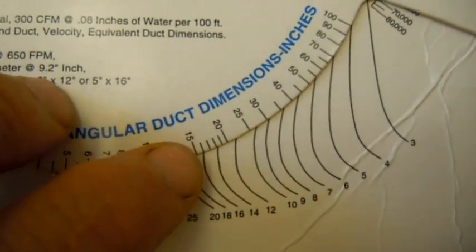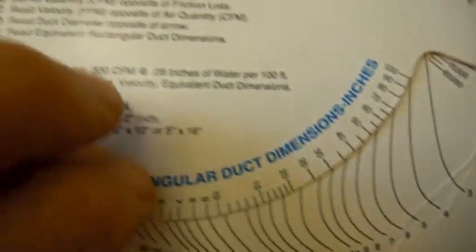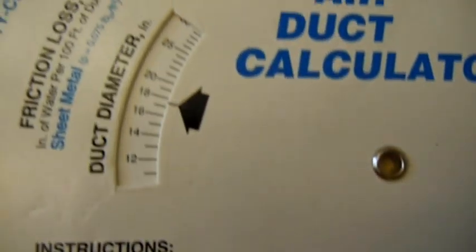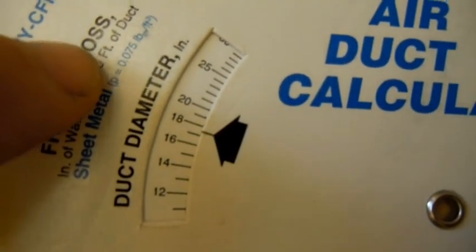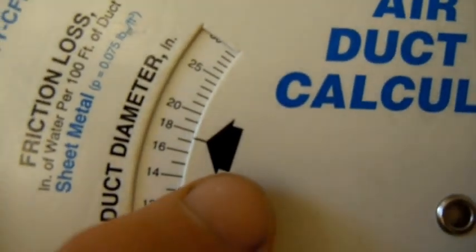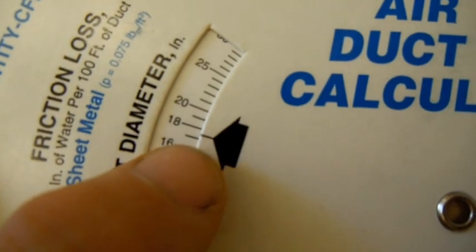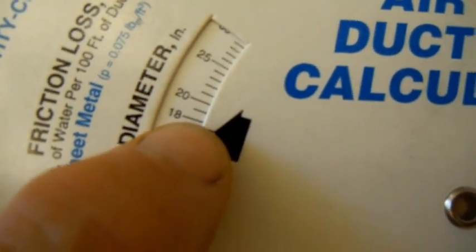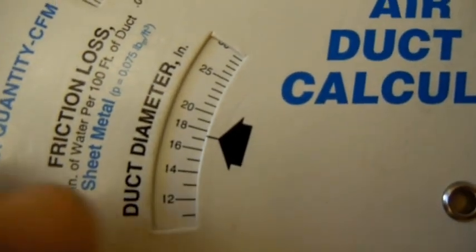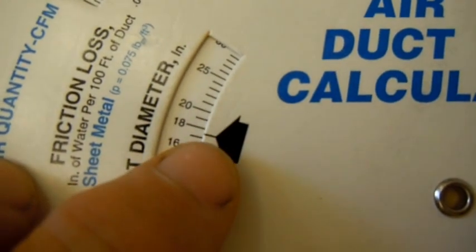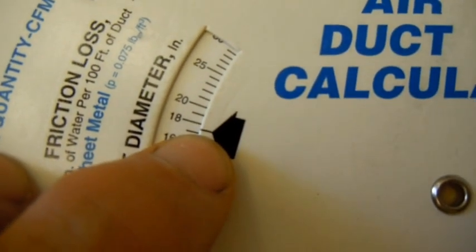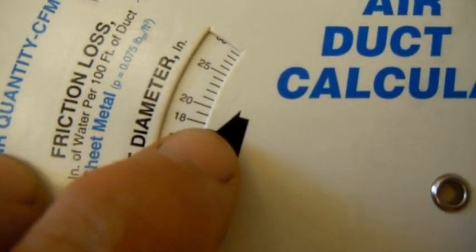So you see that will line up to the equivalent of the round duct to about a little over 17. So really you've got to go to 18 inches. So that means that the same amount of duct space inside diameter is going to be about 18 inches.